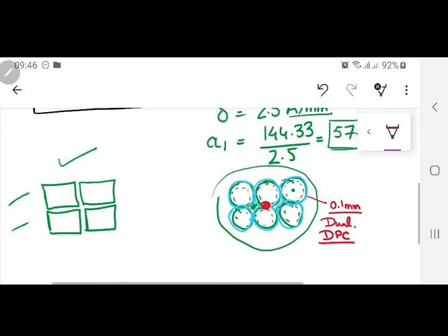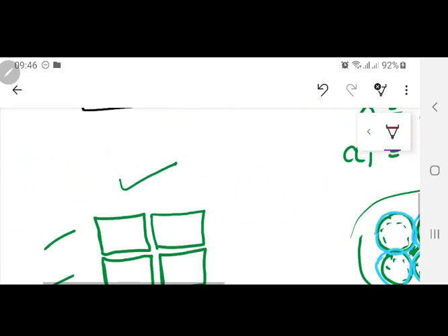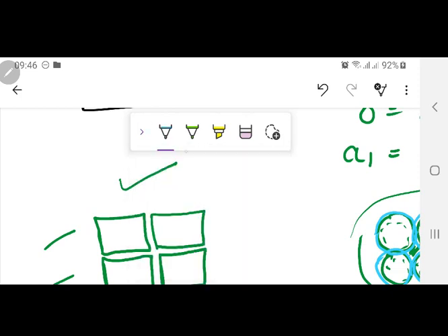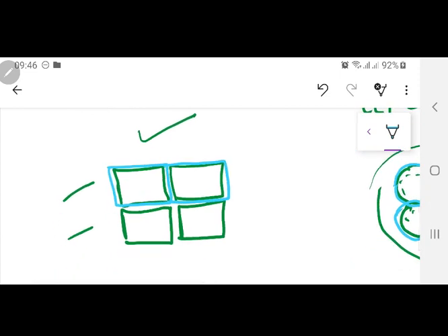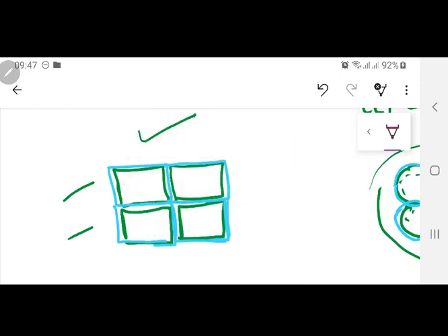Same thing when you are talking about this rectangular conductor: you are going to have the same DPC on each one of these. Now I am not drawing it 2 times, you can just assume that the paper covering has been done 2 times on these conductors. So these 4 over here, they are going to be individual conductors, and this time the skin effect is not going to play a part. It will have the current flowing on each one of them, each behaving as one conductor. But now the problem starts over here.